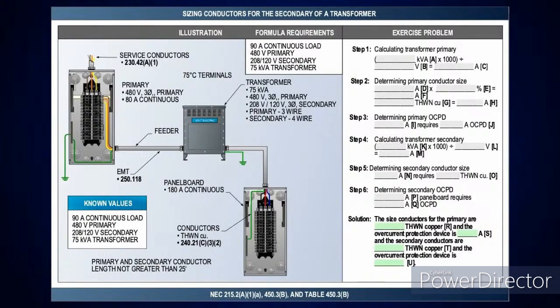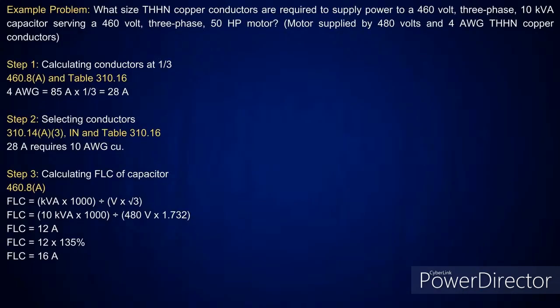Right. Okay? And that's why I try to tell people, the way you go about doing these calculations is really not that hard. It's just knowing I've got to get the amperage for the transformer. I've got to get the amperage for the generator. Every one of those calculations are exactly the same. The only difference is if I had a generator, I had to put 115% on it. In this case, I had a continuous load. I had to take it at what? 125%. Okay? Right. So it depends on what you're looking at, but we try to cover every spectrum here so everybody knows where to find this information in order to perform this calculation correctly.